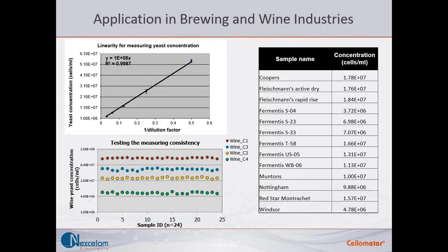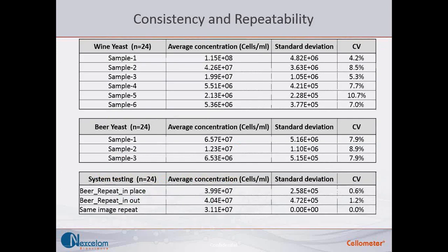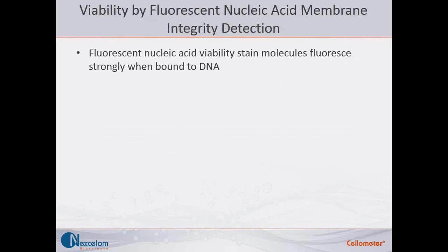For consistency testing: the system demonstrates linearity for measuring yeast concentration from 5×10⁵ cells/mL up to 5×10⁷ cells/mL with a very high R-squared value. Over 24 repeated samples, different yeast types show CVs generally less than 10%. When repeatedly measuring the same sample, CV is less than 2%.